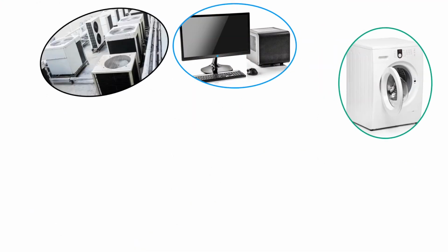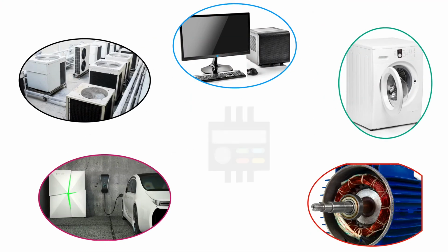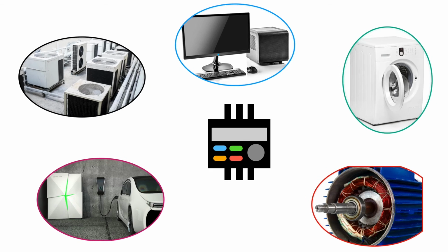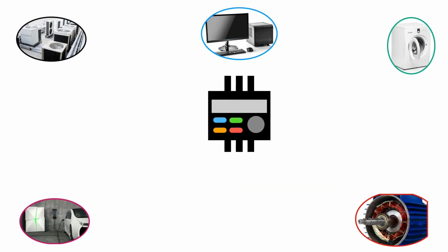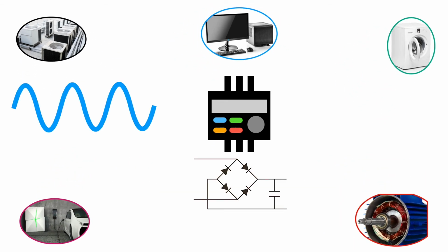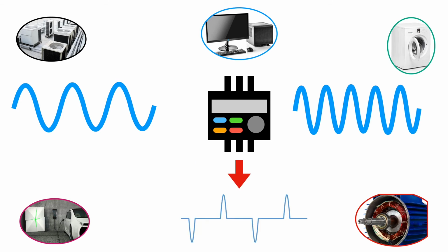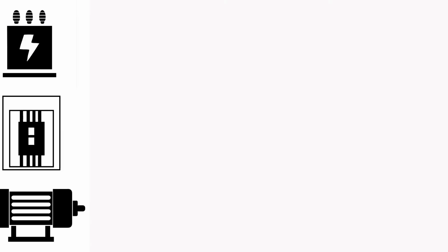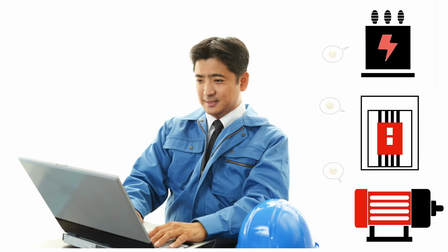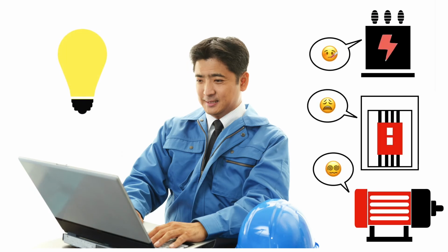Nowadays, for electric devices to work more efficiently, they are equipped with variable frequency drives, or VFDs. Such devices have rectification circuits to convert one frequency to another. However, this distorts the voltage and current waveforms, causing harmonics. Since harmonics cause equipment malfunctions, understanding harmonic components in your power system can help you prevent malfunction.